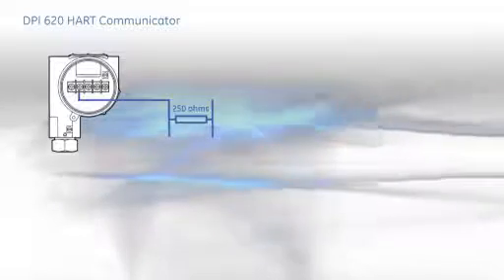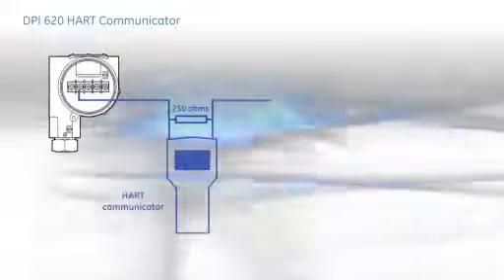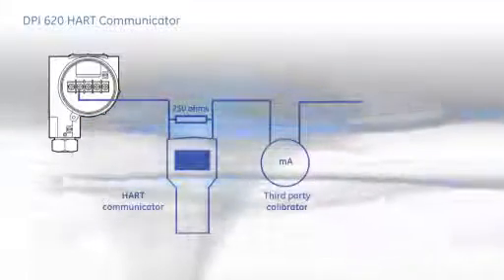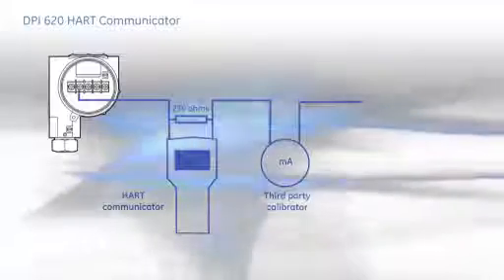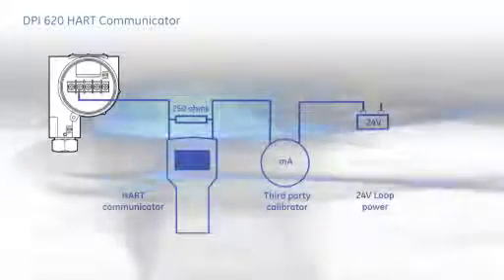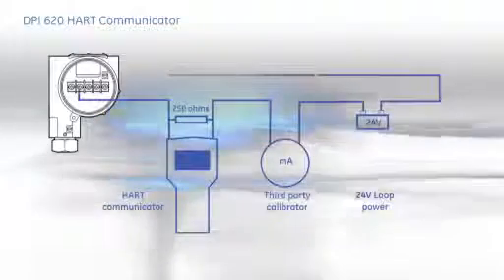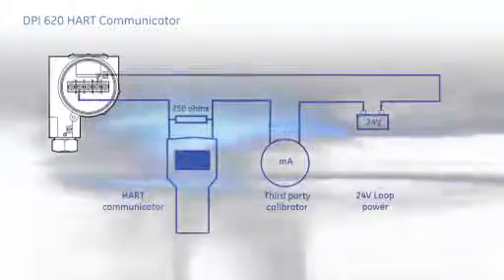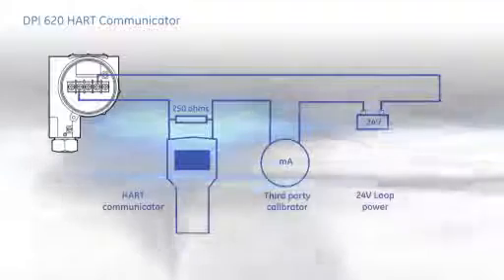Conventional HART communicators require secondary equipment to perform loop setup, trims, and calibrations. This includes a loop resistor, an ammeter, a reference instrument or calibrator, and a power supply. Quite a handful to carry on plant.